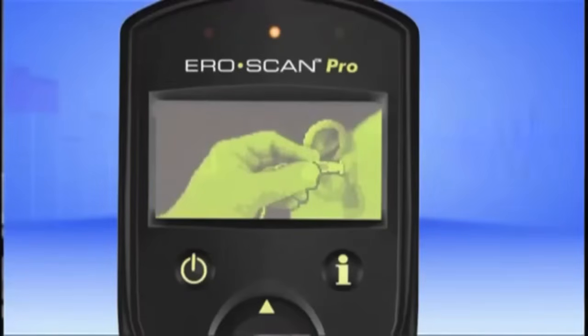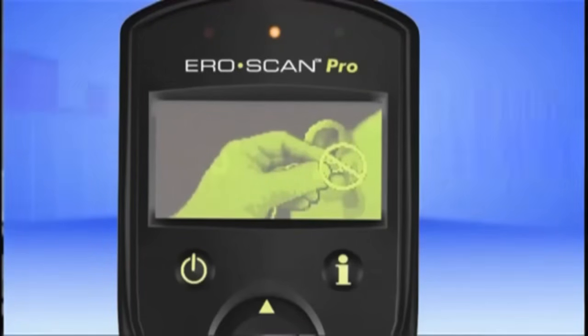This display image indicates the probe is blocked. The ear tip or probe tip might be blocked by cerumen, vernix, or the probe may be against the wall of the ear canal. To correct this, remove the probe from the ear and check for wax or debris in the probe tip. Then reinsert the probe. If no issues are found, the Ero Scan Pro continues with the calibration and testing steps.